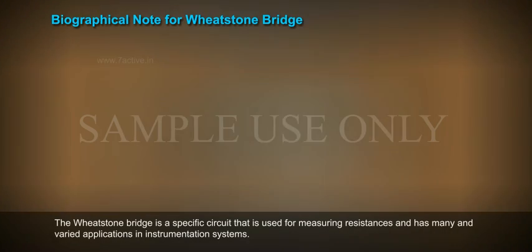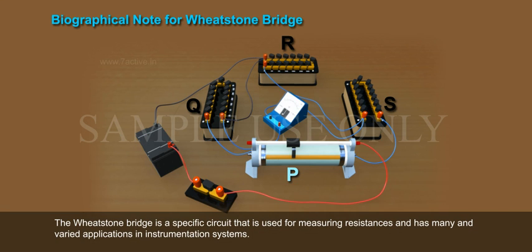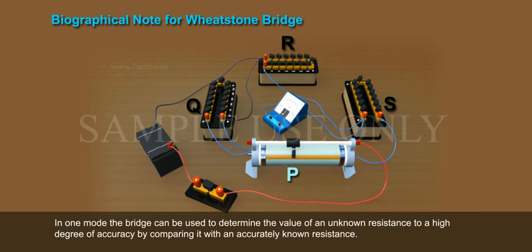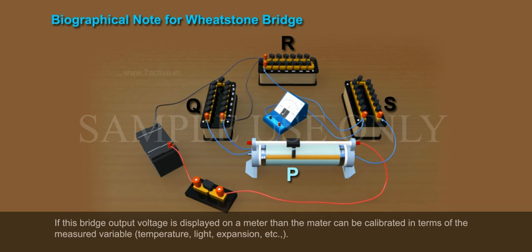The Wheatstone Bridge is a specific circuit used for measuring resistances and has many and varied applications in instrumentation systems. There are two basic modes of bridge operation. In one mode, the bridge can be used to determine the value of an unknown resistance to a high degree of accuracy by comparing it with an accurately known resistance. If the bridge output voltage is displayed on a meter, then the meter can be calibrated in terms of the measured variable: temperature, light, expansion, etc.